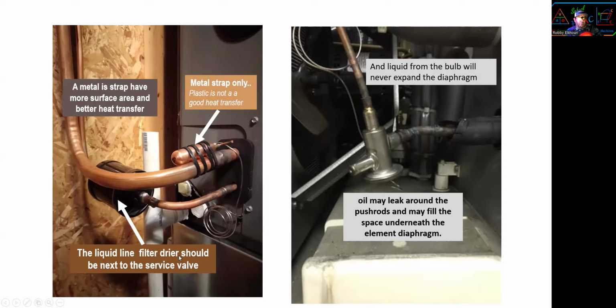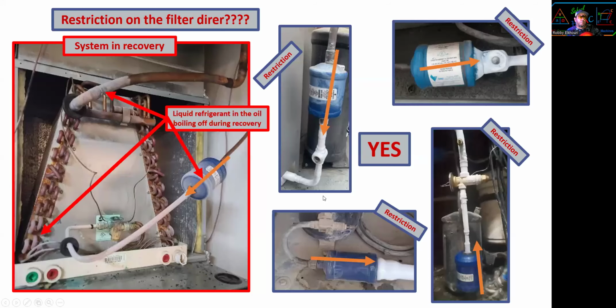The liquid line filter dryer should be next to the service valve. It's the wrong location of the filter dryer here. Do not install upside down because liquid from the bulb will never expand the diaphragm. Oil may leak around the push rod and fill the space underneath the elements. Never install upside down. Next, restriction on the filter dryer.